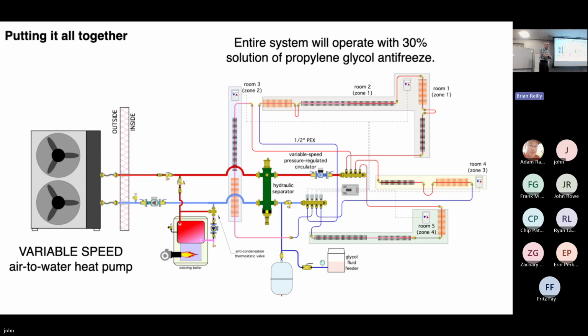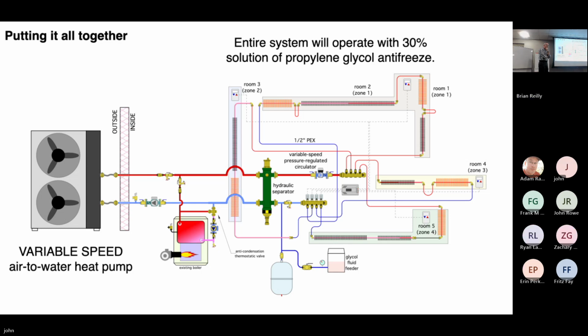We were putting this in a while ago, a residential air to water system. We're trying to suss out putting in a buffer tank, running heating, running cooling. If you put in a buffer tank and you're heating, it's Vermont. Sometimes it's 40 degrees in the morning, and then the sun comes out. It is 70 degrees by the end of the day, and now the house is hot because the sun is hitting the south side.